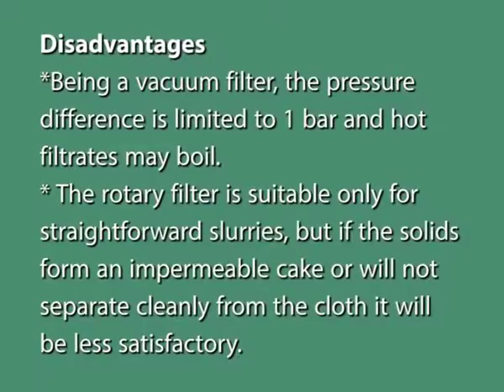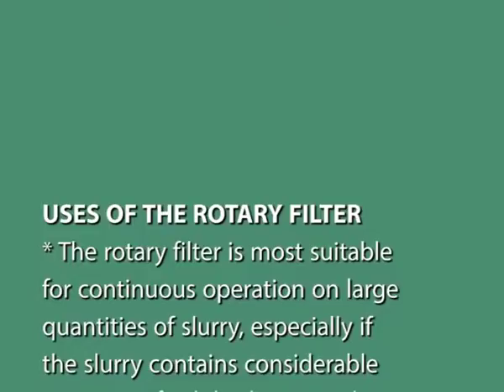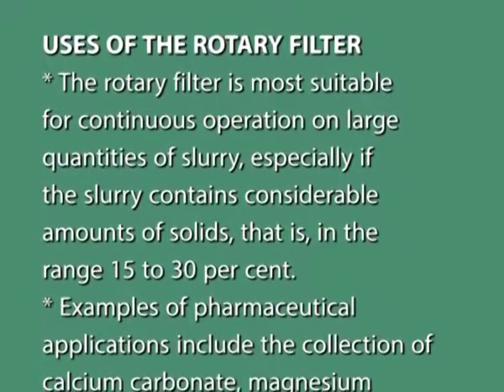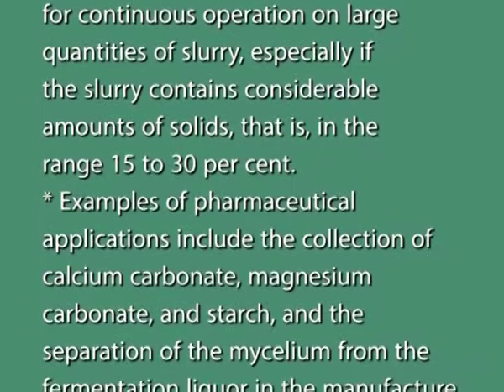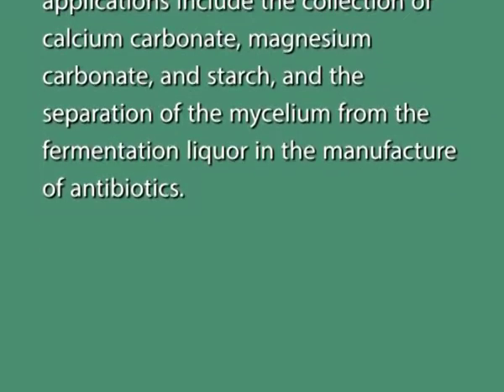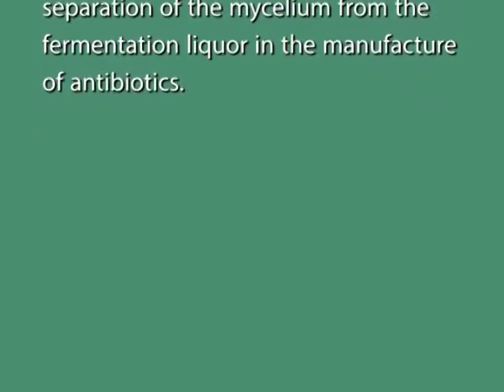Disadvantages of the rotary filter include that the system is complex with many moving parts and is very expensive. The cake tends to crack due to air drawn through by the vacuum system so that washing and drying are not efficient. Being a vacuum filter, the pressure difference is limited to 1 bar and hot filtrates may boil. The rotary filter is suitable only for straightforward slurries. The filter is most suitable for continuous operations on large quantities of slurry especially if the slurry contains considerable amounts of solids in the range of 15 to 30 percent. Pharmaceutical applications include collection of calcium carbonate, magnesium carbonate and starch, and the separation of mycelium from fermentation liquor in the manufacture of antibiotics.